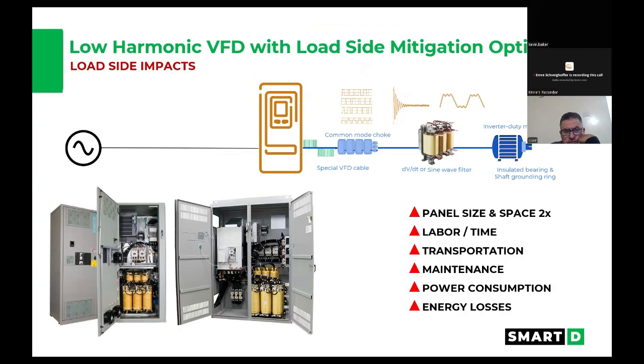Yeah, there was a lot of line noise. So common mode voltage causes that line noise, but also on the front end. We're looking at the back end right now, but on the front end, remember, there's also harmonic distortion that happens, and that adds a lot of emissions and noise into the grid, affecting everything else connected to it. So if you've got sensitive equipment, like that farm did — it was a highly automated farm — all of their equipment was being affected by these emissions happening from the VFD on both sides.